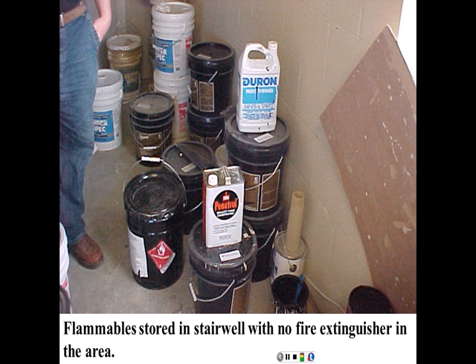Here are, for example, flammables stored in a stairwell with no fire extinguisher in the area. That's a big violation.